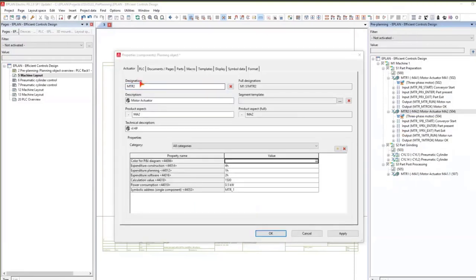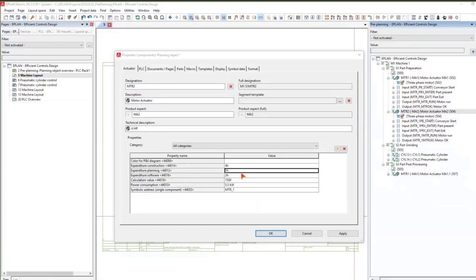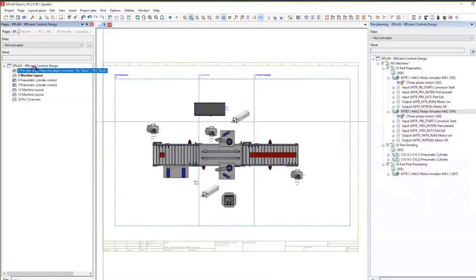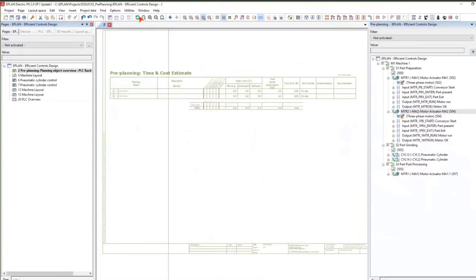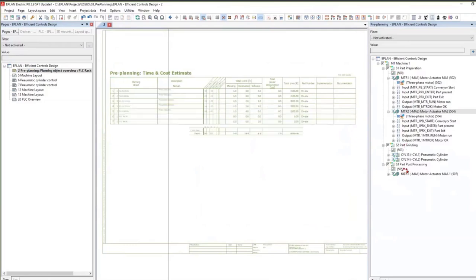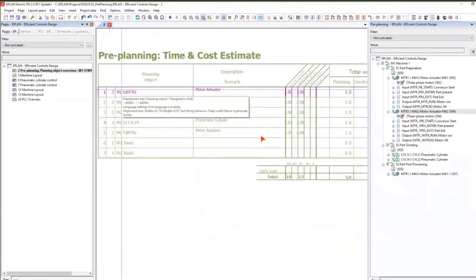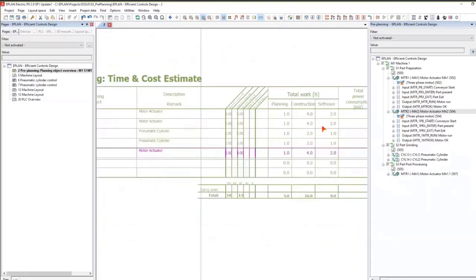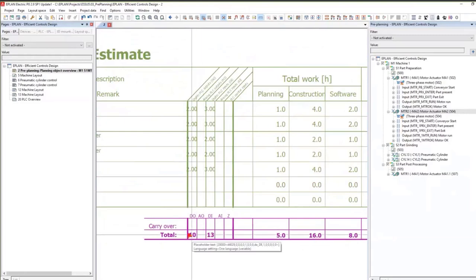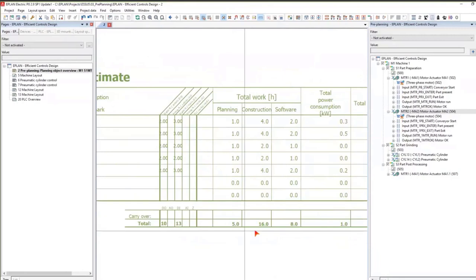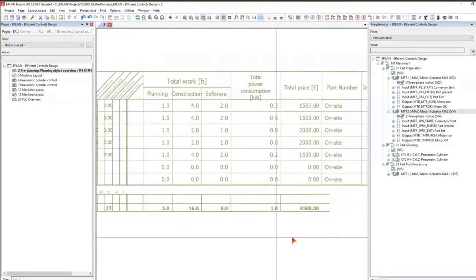Behind each object, I also have my data — descriptions, technical descriptions, and information regarding construction, planning, and software. For each object, I can identify how long it will take to build, plan, and program the system, and how much it will cost, all for quoting purposes. Updating the report now captures all my control equipment — pneumatic cylinders, three motors — identifying how many IOs and signals are needed: 10 digital outputs, 13 digital inputs, 5 hours of planning, 16 hours of construction, 8 hours of software, for a total price of $8,500.